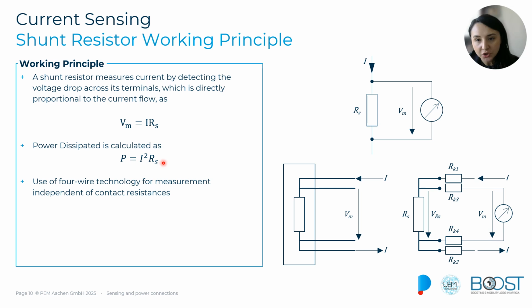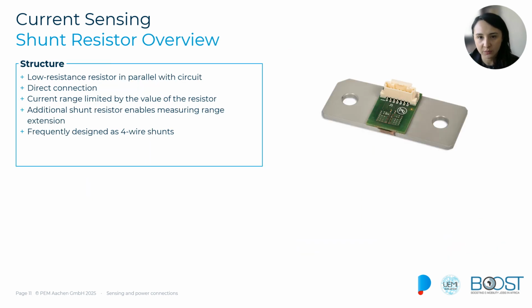To accurately measure both low and high currents, the shunt resistance must balance power and range. At low resistance, we reduce power dissipation but sacrifice precision in detecting small currents. At high resistance, we improve measurement accuracy at low currents but increase power losses at high currents. So there is a trade-off the designer has to manage every time.